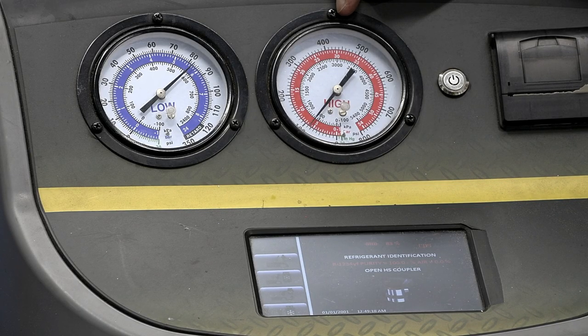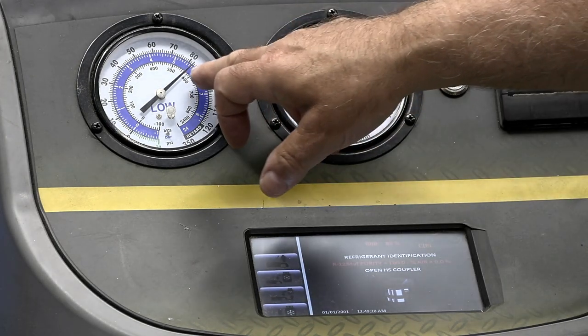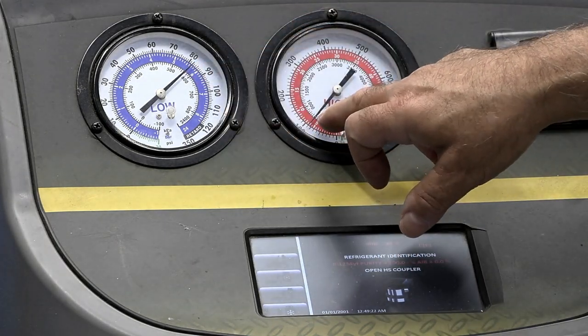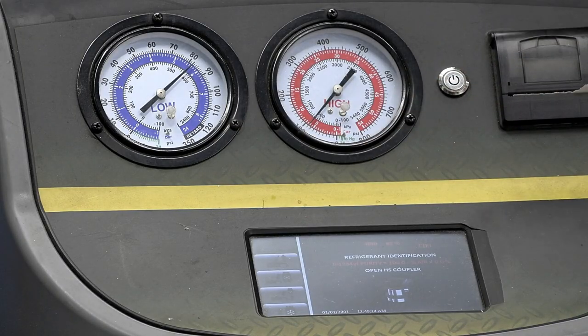Now notice, look at that. You've got about 82 and you've got 82, both gauges are equal. Why is that important? Well, that tells me there's not a clog in the system. Does that make sense?